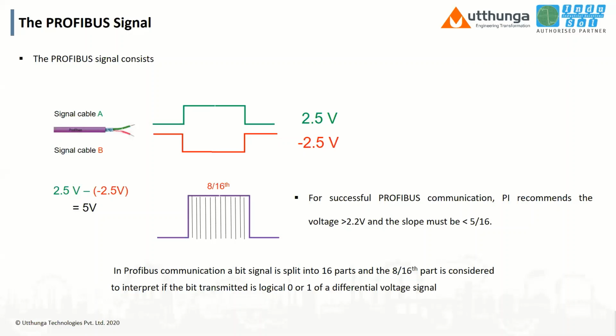In Profibus communication, a bit signal is split into 16 parts, and the 8 by 16 part is considered to interpret if the bit is logical 0 or 1. As per the PI standard, the recommendation is that the voltage should always be greater than 2.2 volts and the slope must be less than 5 by 16.